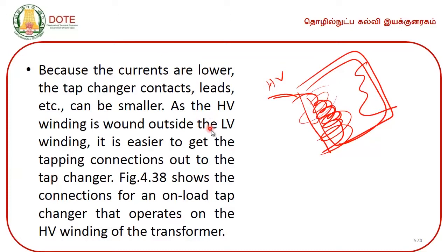As the HV winding is wound outside the LV winding, very near to the core the LV winding will be present. Upon construction of the LV winding on the limb of the core, then comes your high voltage winding. So, as the high voltage winding is wound outside the LV, that is low voltage winding, it is easier to get the tapping connections out to the tap changer.